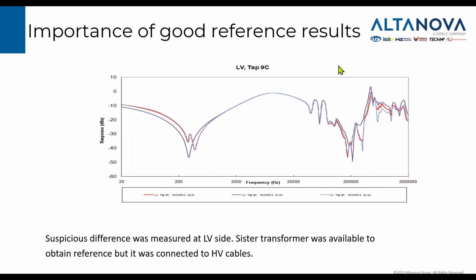And they were reluctant because it was connected to the cable on the high voltage side. Disconnecting the cable is a multiple-hour, long-duration job, and they didn't want to do it. Then I said, okay, maybe we do not disconnect the high voltage side, we can just unearth it on the other side of the cable, as long as it's proven it's not inducing any voltage. So we did that. They disconnected the earthing, they measured potential on the terminals, everything was safe. And then I did the same on the transformer which was previously tested by me. That one was disconnected from the high voltage cable. I reconnected it to that high voltage cable by shorting leads and measured the low voltage side again. And this is what I'm presenting here.